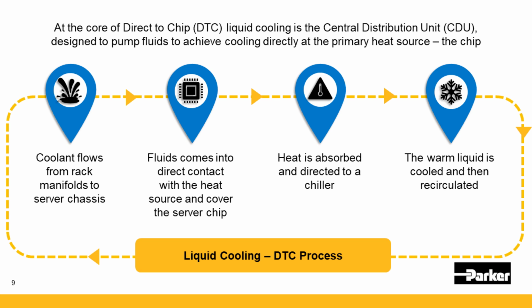So direct-to-chip liquid cooling, you'll commonly see it as a cold plate or cold plate loop. The heart of it is getting the coolant, whether single phase or two phase, directly to that main heat source. It's typically the chip, a GPU, a CPU, or any of the more exotic processing units out there today. Sometimes it's also used for other parts of the IT gear, but it doesn't go through everything. Usually you're targeting those main heat generators.